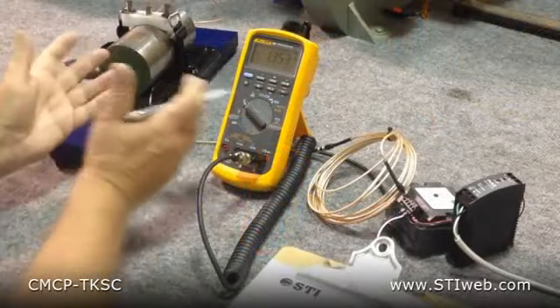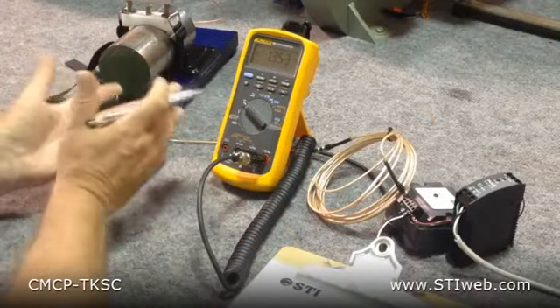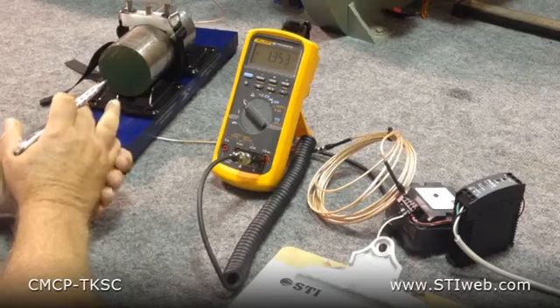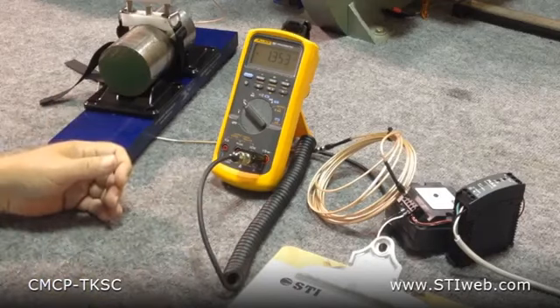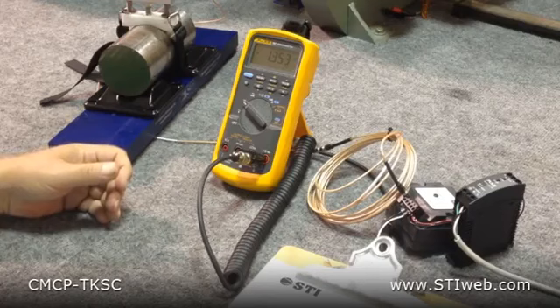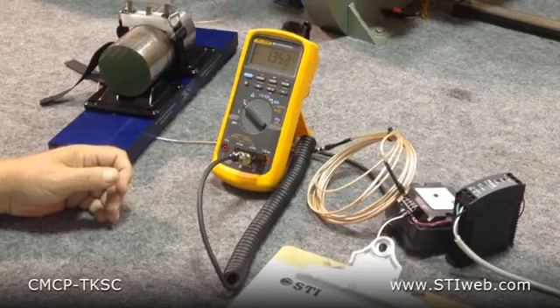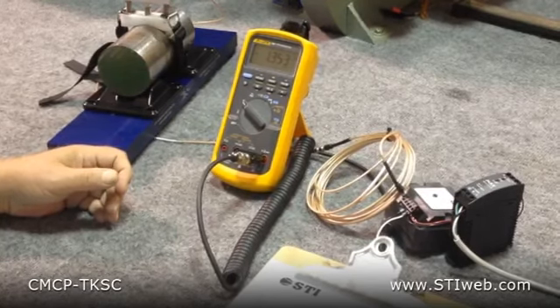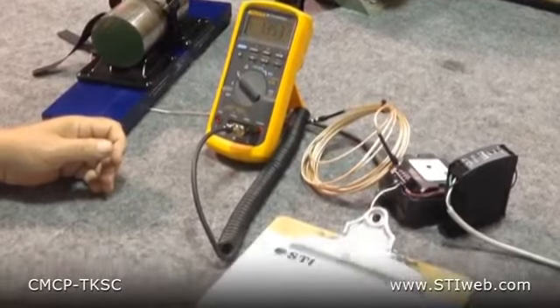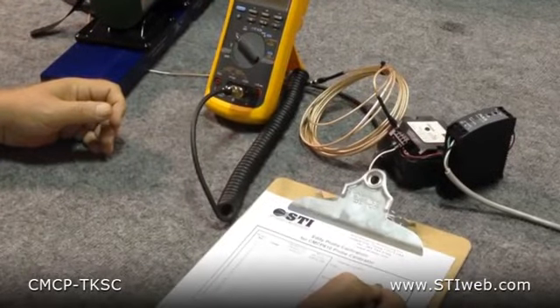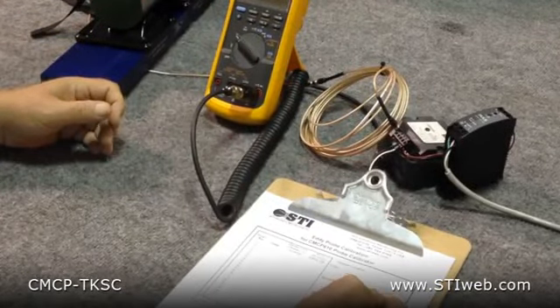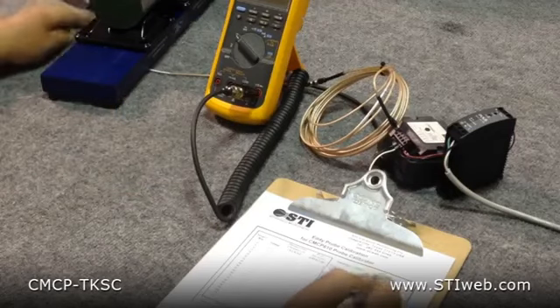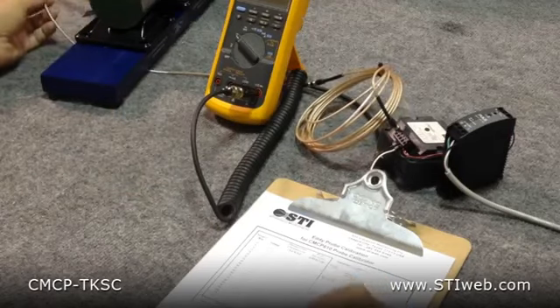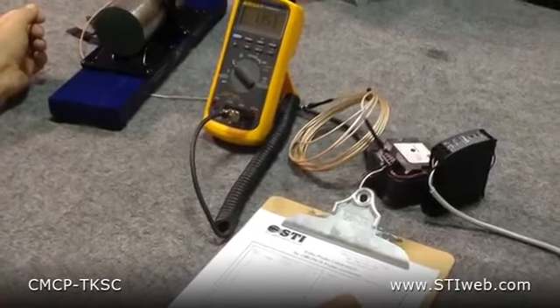What we're going to do now is we have a choice of running a complete probe calibration graph. We have an Excel sheet available on the STI website under eddy probes that automates the system. You enter the voltages every 5 mils, and it'll automatically graph it for you. You need to enter things like the proximeter serial number and model number, cable, and eddy probe itself. Customers like this because it ensures that they know what they have. You also can take a very quick approach to this too.